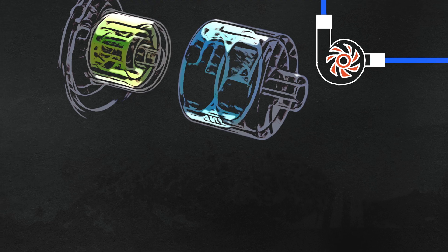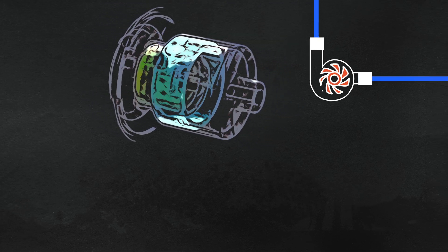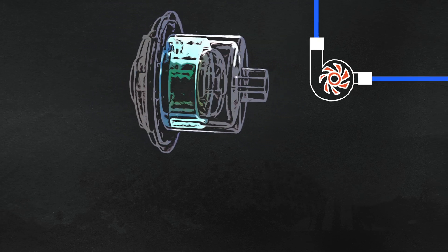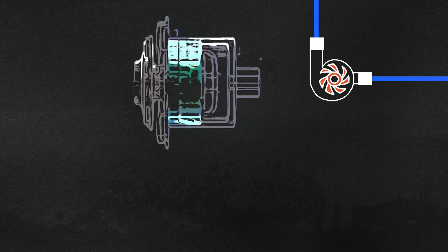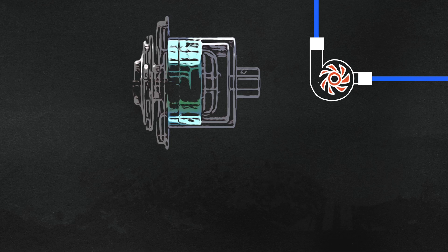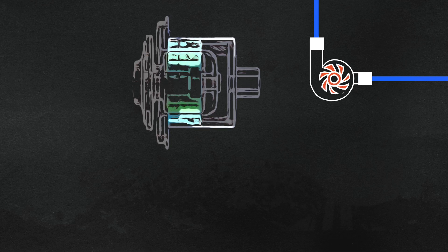Next, let's talk about pumps. We talked about roller pumps previously, which are used with lower flow systems such as dialysis machines. Most modern ECMO circuits, however, use centrifugal pumps.